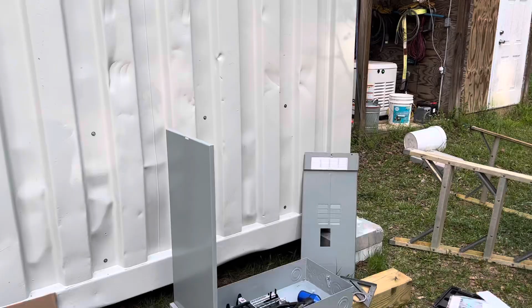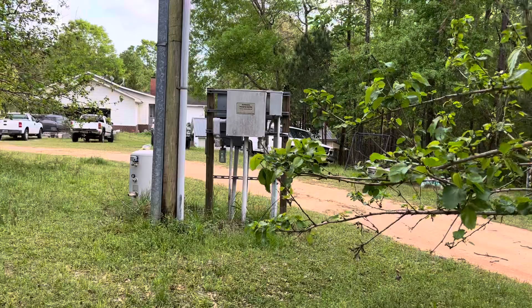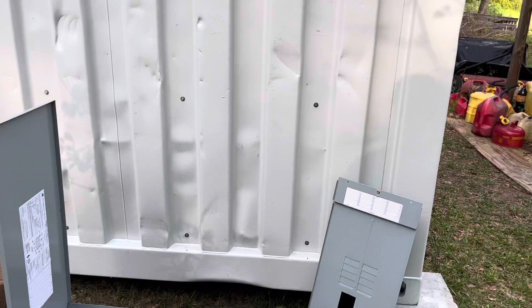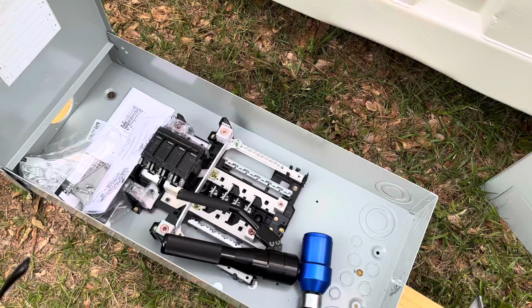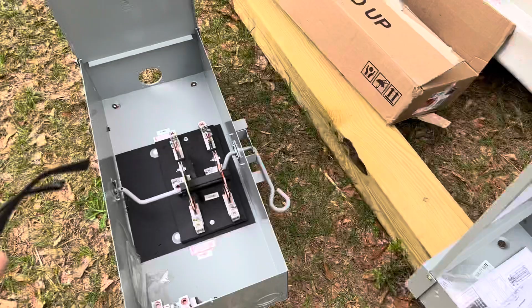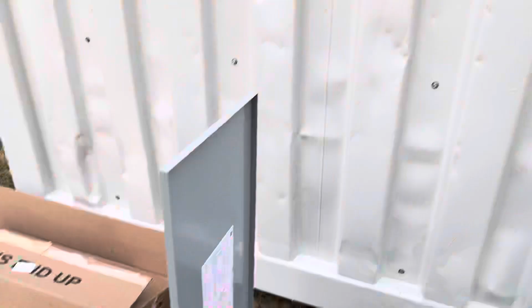But my power is going to come from over here from my utility. My meter is on the other side of that gear. I'm going to come down, dig it, bury the cable with some conduit, and then mount my first breaker box on this wall. This box right here. And then I will use these feed-through lugs here to feed into this manual switch, which is going to mount right adjacent to this breaker box on the wall here.